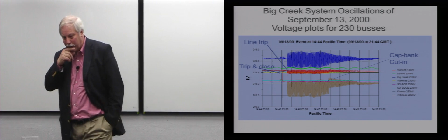What you're looking at here is a real oscillation on the Southern California Edison power system on September 13th, 2000. What you're looking at is the 230 kV voltage here in normal pre-fault state, and then these little wiggles here represent a fault, trip, high-speed reclose; fault, trip, high-speed reclose; and then finally fault, trip, lockout.